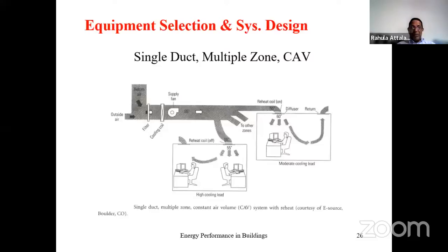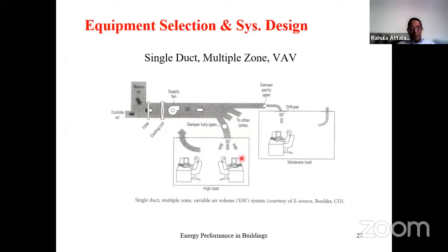And in contrast to that, we also have the same thing with variable air volume. In the same example, the temperature would remain the same, 55 Fahrenheit, but the quantity of cold air supplied varies. Here the load is high because the internal load is higher than this. So you need a lower flow rate here, and here you need a higher flow rate for the higher load. True enough, you have to reduce the flow by choking or damping the flow rate, which will cause some energy loss. However, here you maintain a constant temperature. Therefore, overall energy performance is much better in the variable air volume configuration compared to the constant air volume configuration.